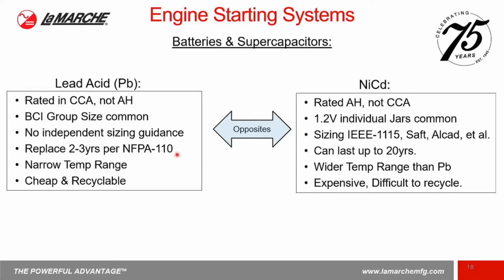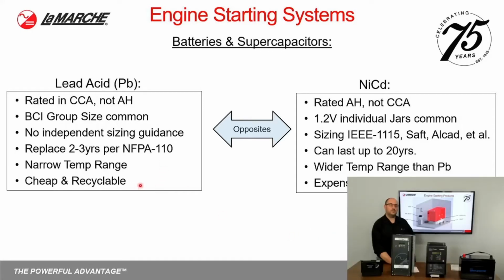The leads will normally need to be replaced every 2-3 years per NFPA, but the NiCads will last a long time, 20 years plus, and have a wider temperature range. But the thing with the NiCad is they're expensive and they're difficult to recycle. So a lot of people went with the lead acid battery because they're cheap and easy to replace. And when we say recyclable, a lead acid battery is actually 99% recyclable.